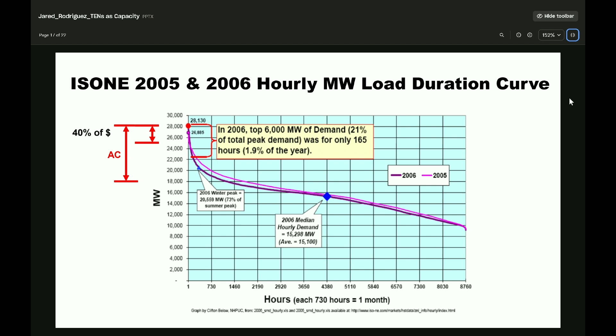So I argue all that matters is peak demand at the design condition - in the winter, when it's coldest, when you're designing a building to withstand particular low temperatures or conditions over a prolonged period, the worst condition you could design for. Because the building needs to withstand that, or else in the off chance that it happens, you're out of luck.